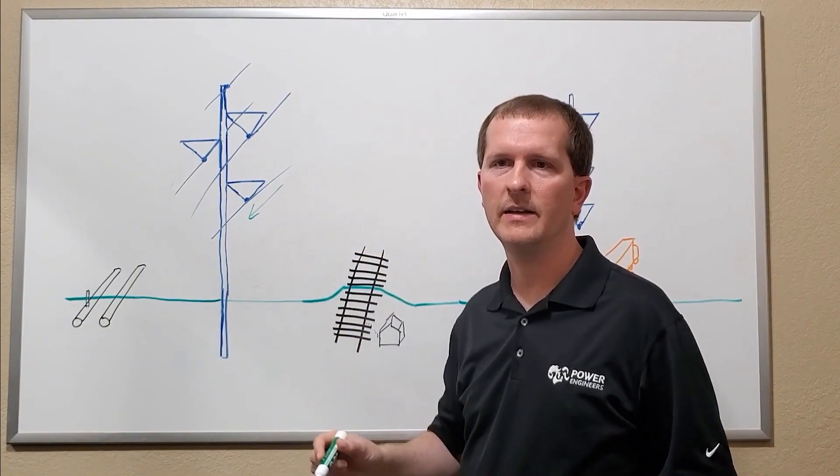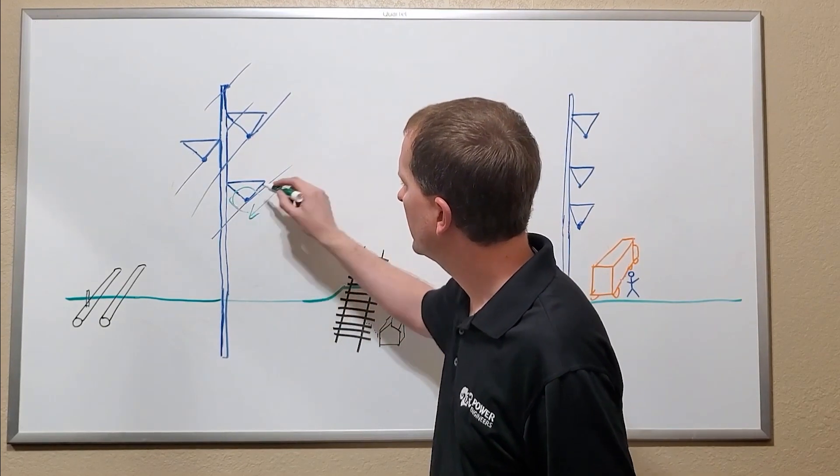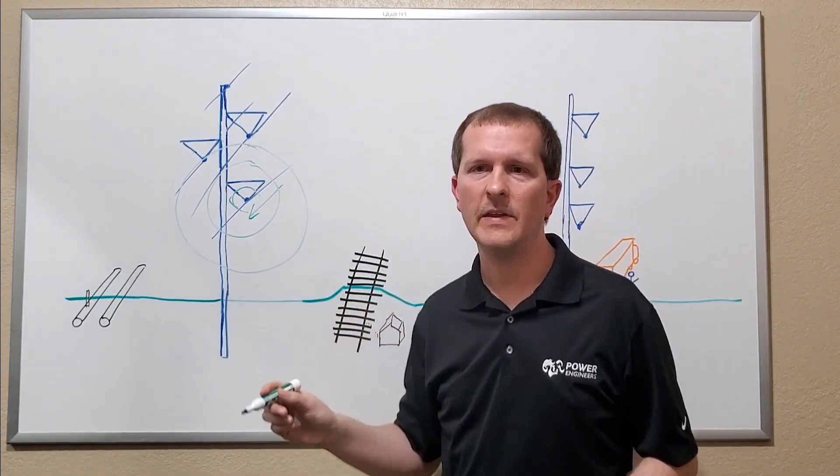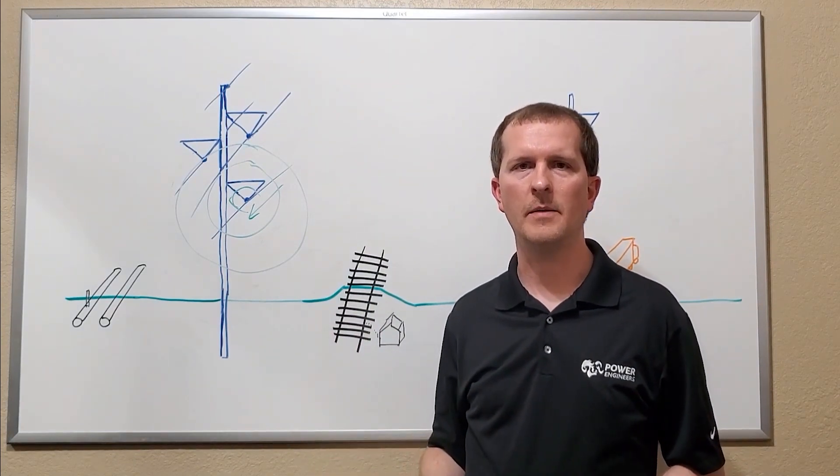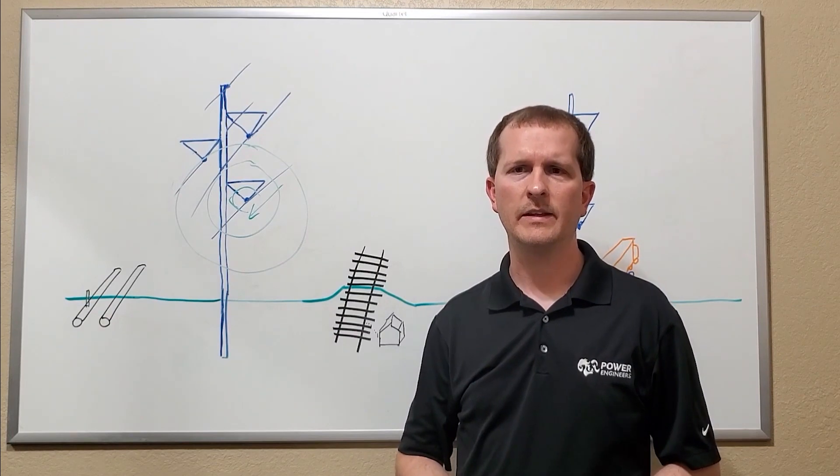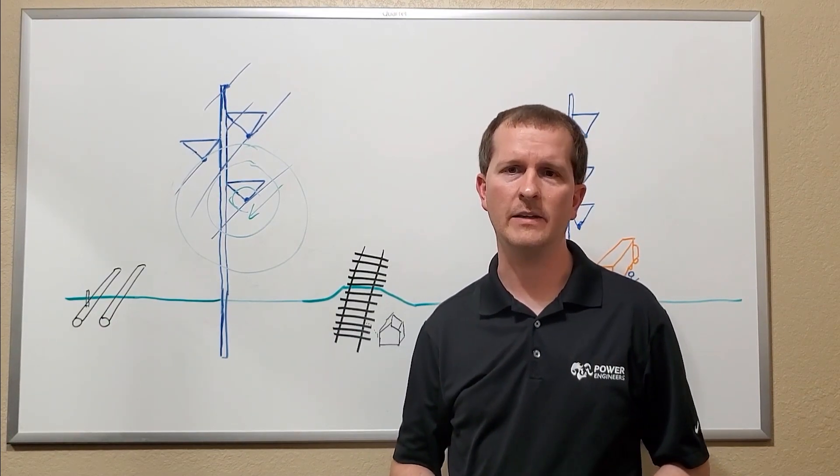For example, as current flows through a transmission line, it will create magnetic fields that radiate out from each of the conductors. These fields can couple onto long parallel objects, such as pipelines and rails, inducing a voltage that can pose a risk to both workers and to equipment.